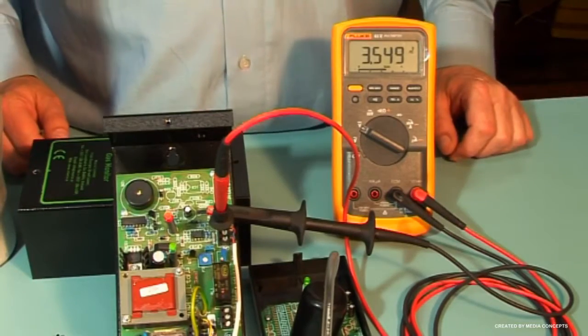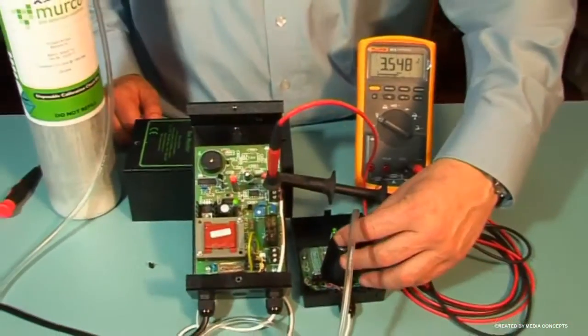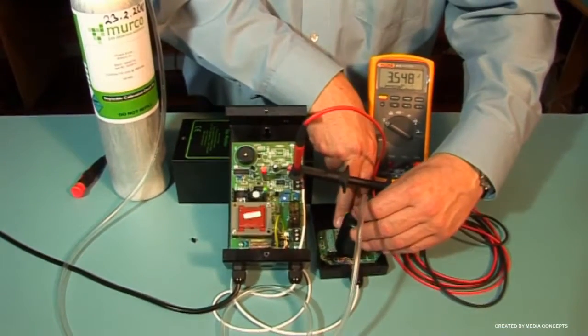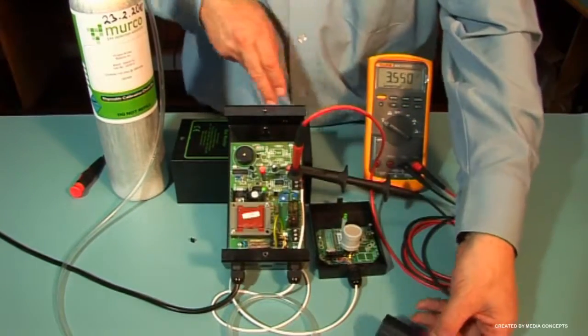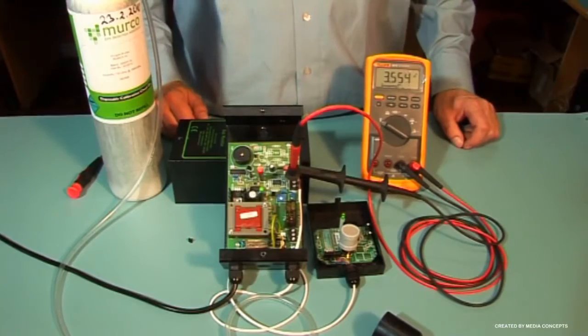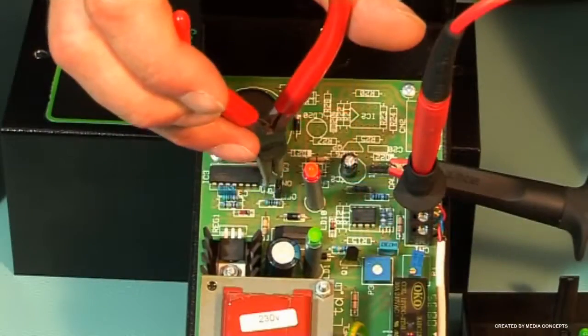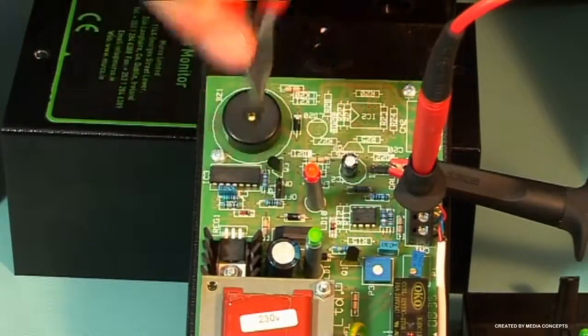Remove the gas and allow the sensor to fully recover and record this new standby voltage for future calibration reference in the system log and on the rating label. The sounder can be silenced by removing jumper JP1.